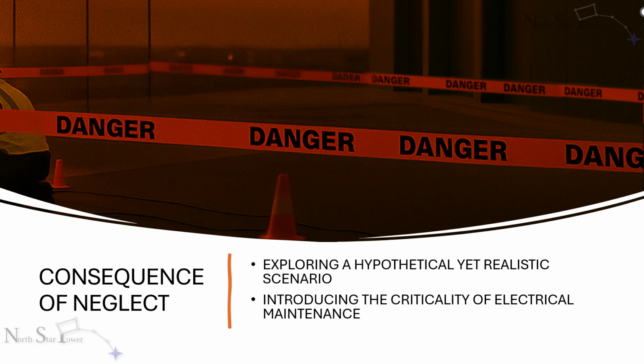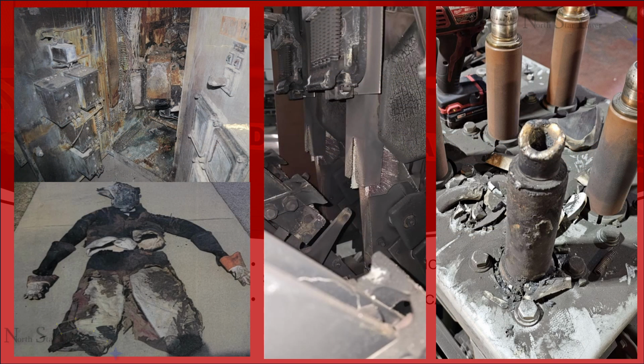Afterward, OSHA investigates and finds that although infrared testing had been performed, none of the standards outlined by the NFPA were followed or documented. The real issue, mechanical binding from dried lubricant, was not detected. Had qualified personnel been brought in to perform thorough inspections, the entire disaster could have been prevented, while hypothetical. This scenario closely mirrors real-world events that occur with disturbing frequency.